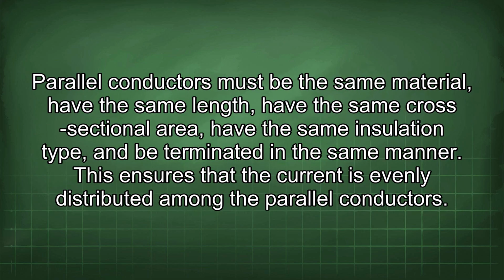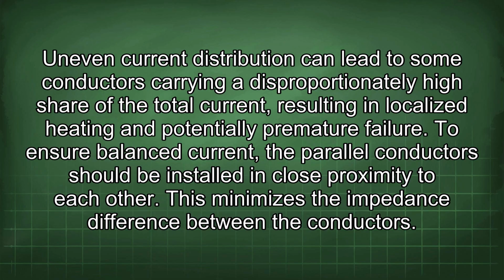Parallel conductors must be the same material, have the same length, have the same cross-sectional area, have the same insulation type, and be terminated in the same manner. This ensures that the current is evenly distributed among the parallel conductors. Uneven current distribution can lead to some conductors carrying a disproportionately high share of the total current, resulting in localized heating and potentially premature failure.